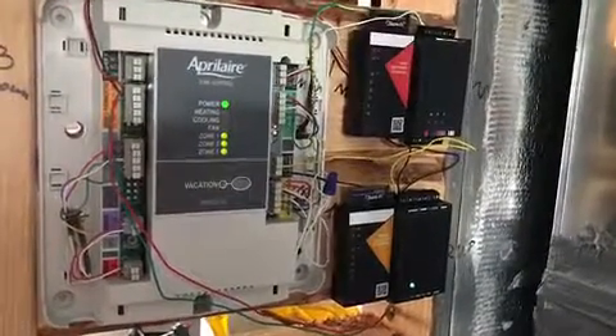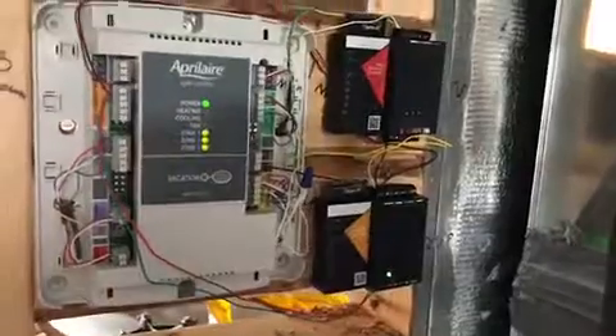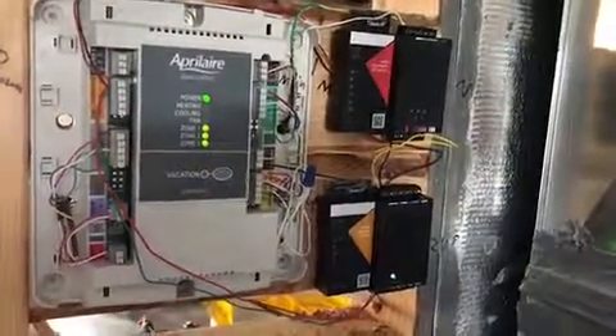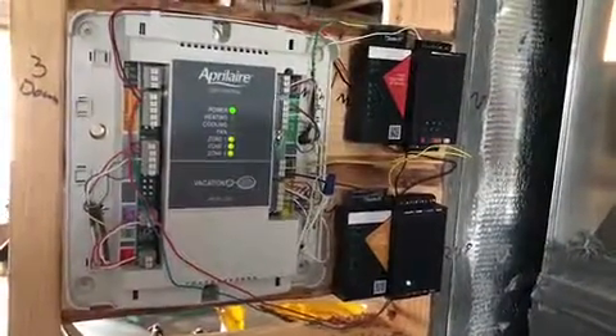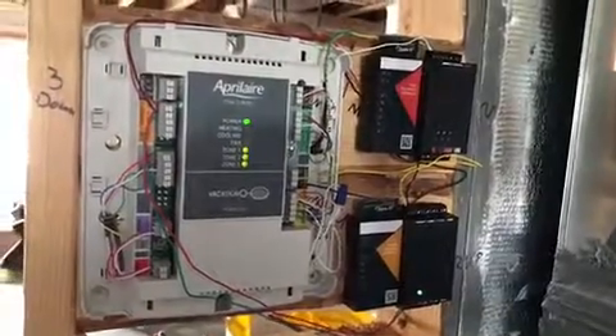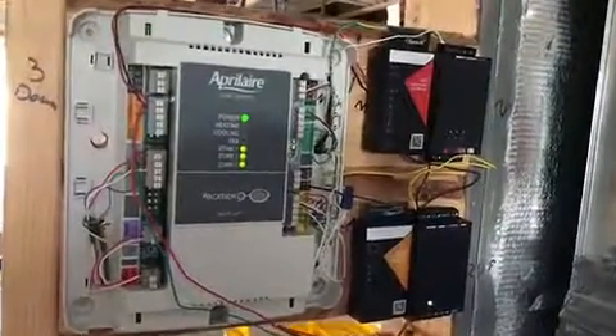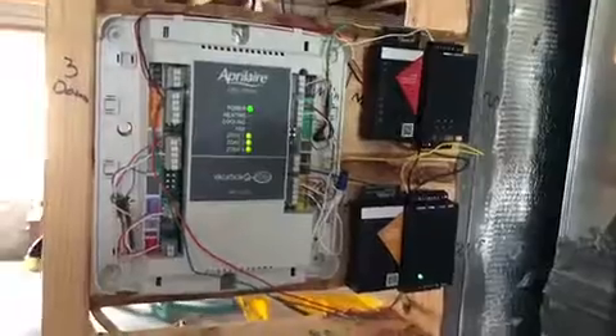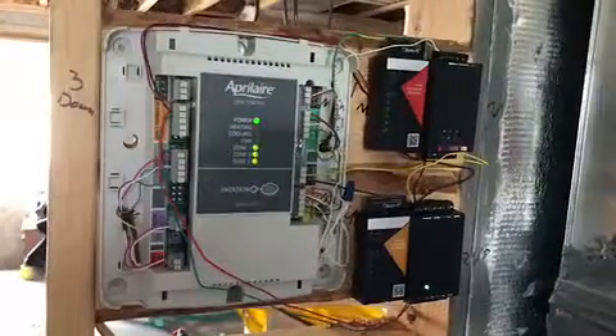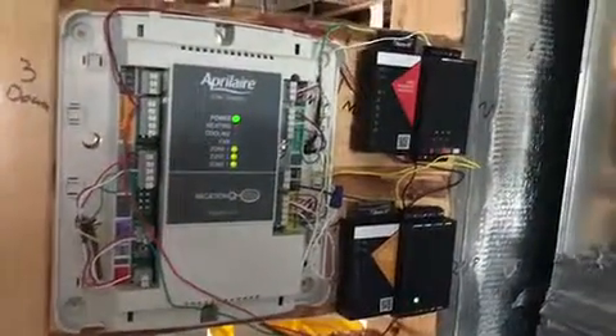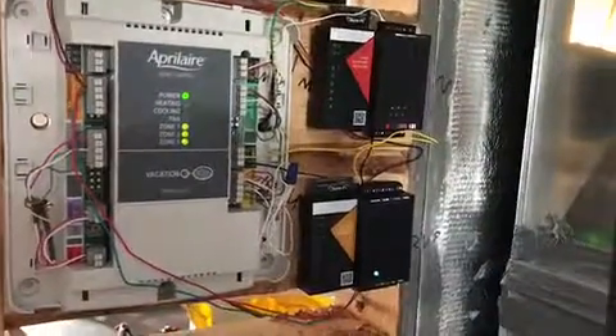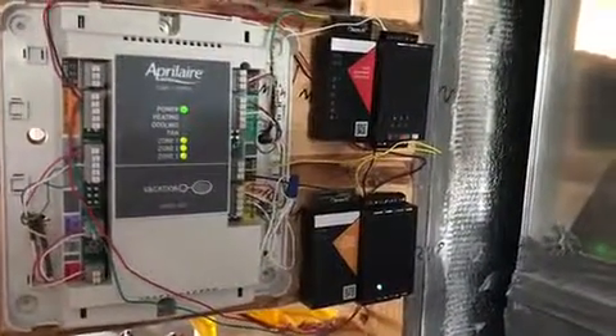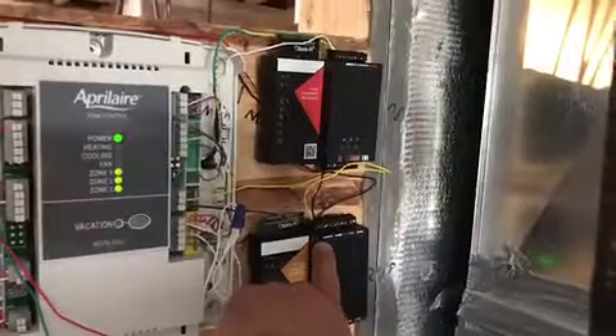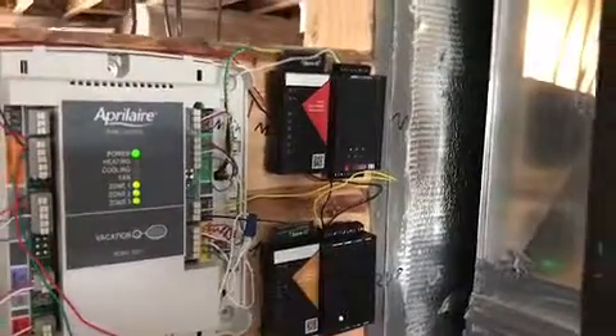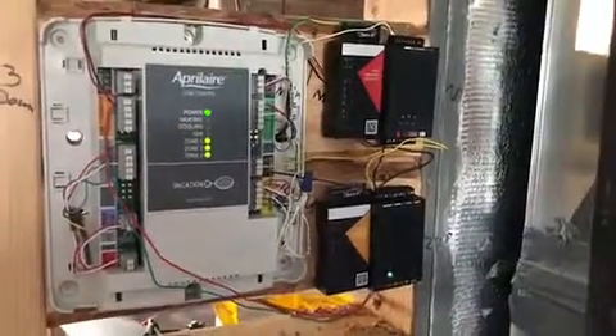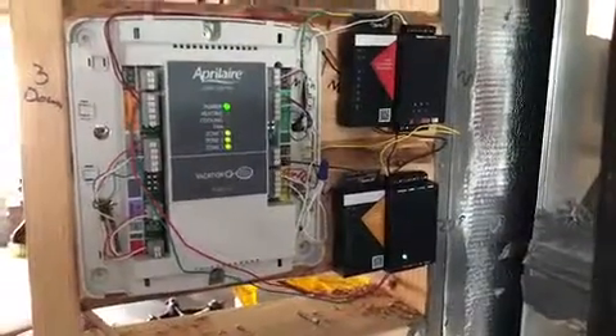And we had a situation where we thought it would run on a 0 to 10 volt situation, like a lot of dampers do. This particular one ended up being a 24 volt straight relay. So normally open, normally closed, and the Aprilaire zone controller would just close it when the desired temperature was reached. But luckily we have that figured into that analog bridge. We have a 24 volt relay that can be set for normally open right there. So we were able to connect that, and I'll show you working on the other side.